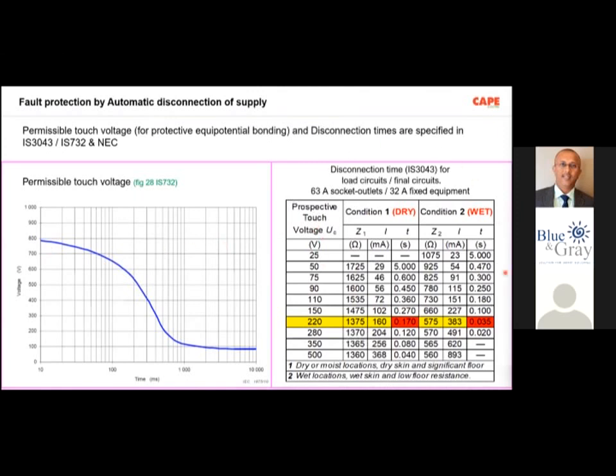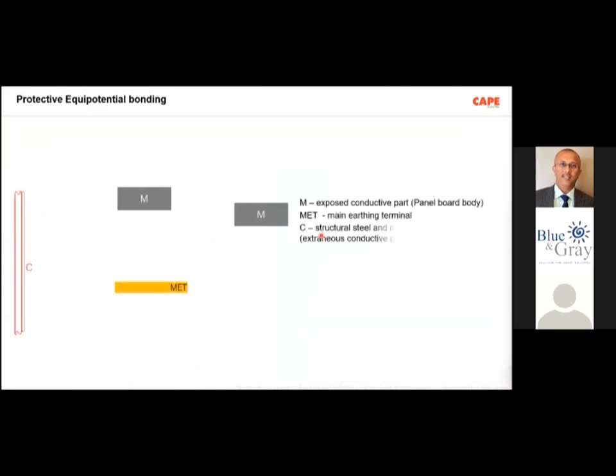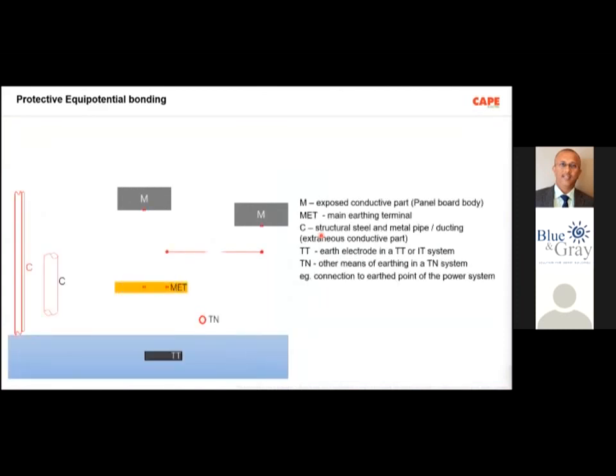Then here, this is the disconnection time. What do we mean by disconnection time? It means the protective device should trip within a certain time in order to achieve safety. So in order to make the second test, which is called the efficiency of automatic disconnection of supply, first you should understand what kind of safety measure is implemented in your building. Then you must understand how the protective equipotential bonding is carried out.